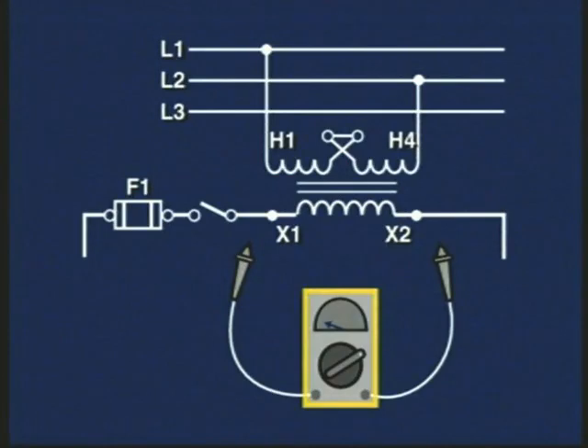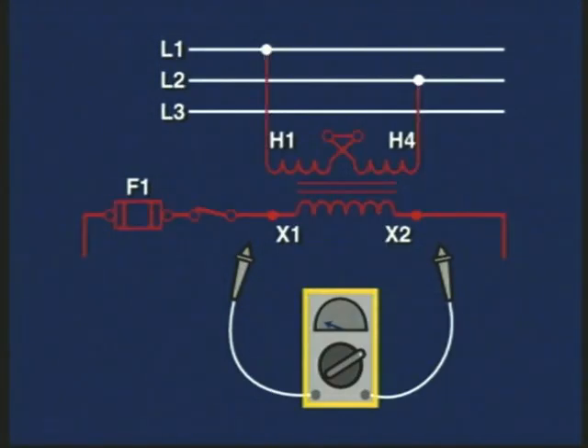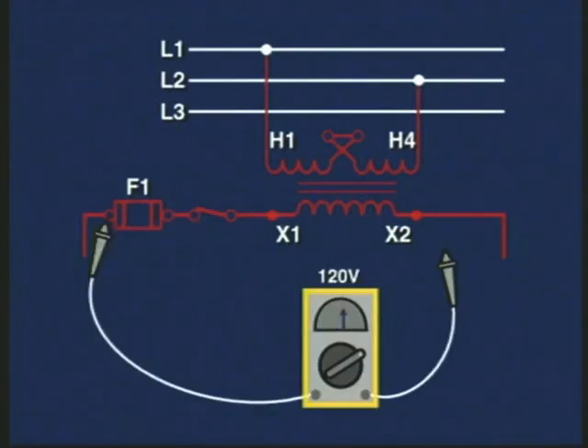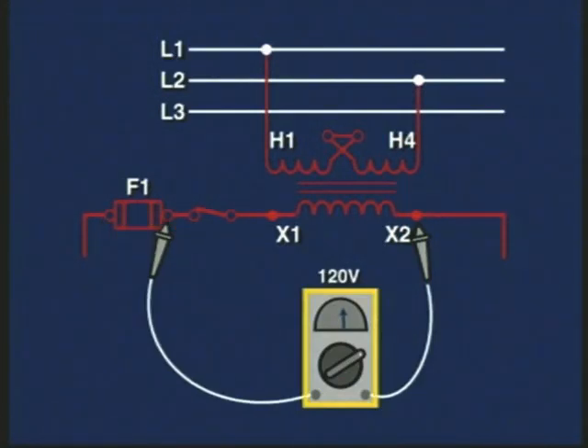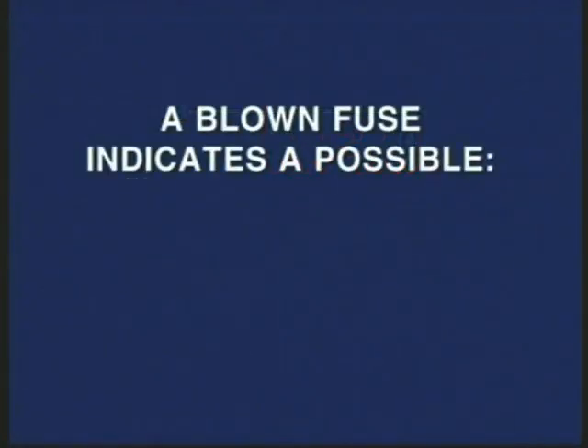Next, we would check the fuse protection to the control circuit. So we close the disconnect and measure the voltage from the load side of the fuse to the X2 side of the transformer. We should read close to 120 volts AC. If no voltage is read, then the fuse is bad. To make sure that voltage is present after the disconnect, we could also put the voltmeter lead in the supply side of the fuse to ensure that the disconnect is indeed okay. If the fuse is blown, we would need to replace it.